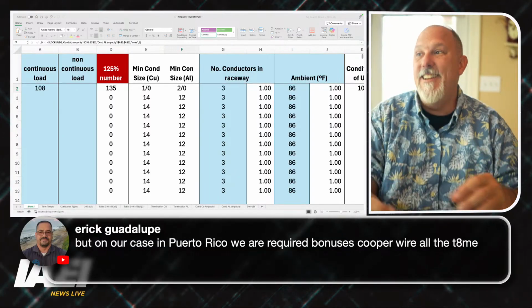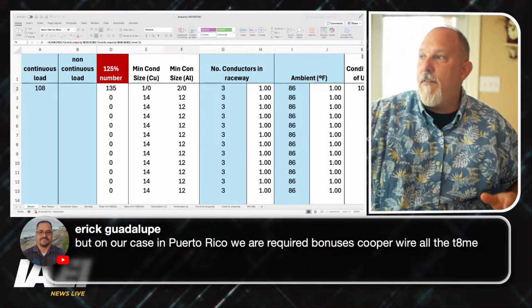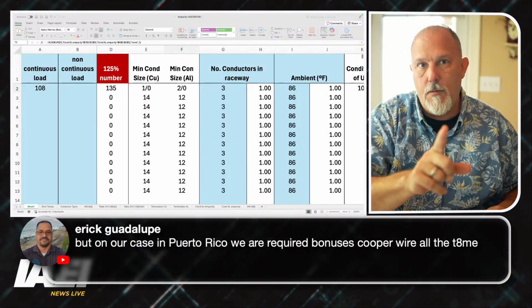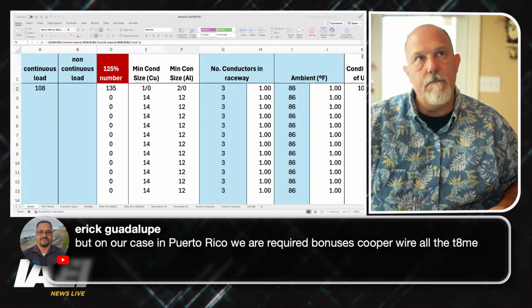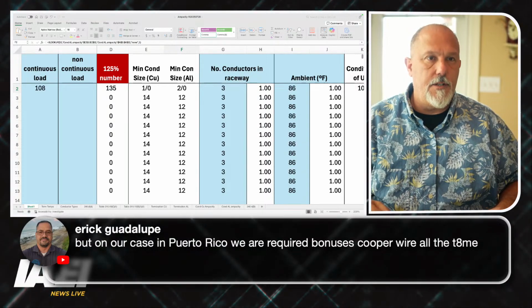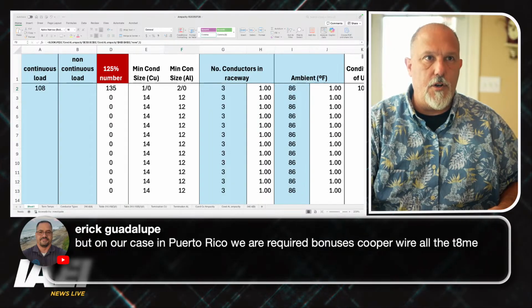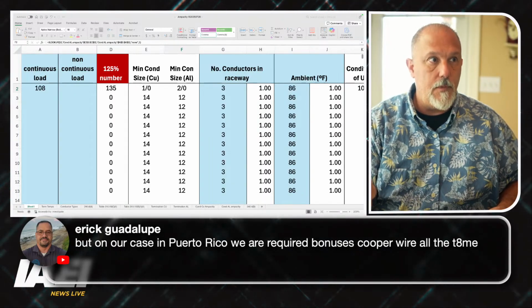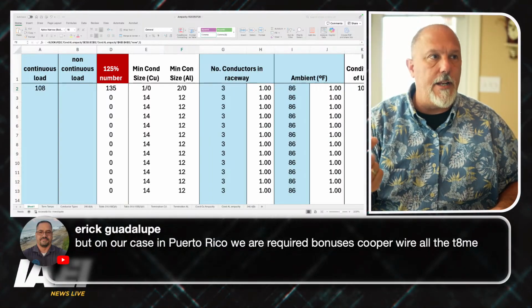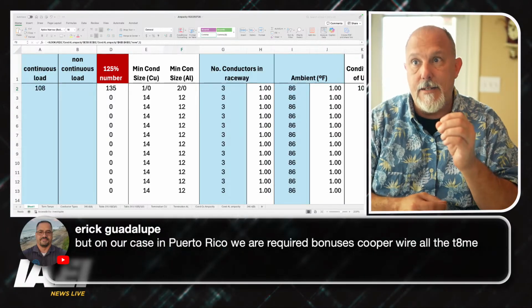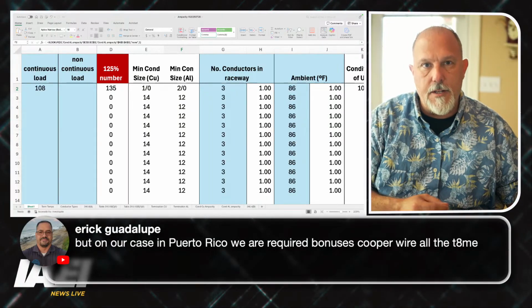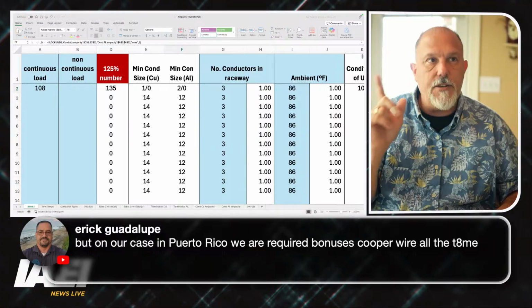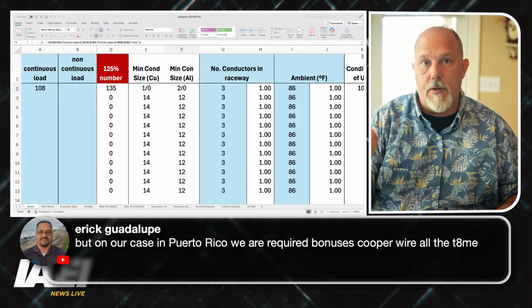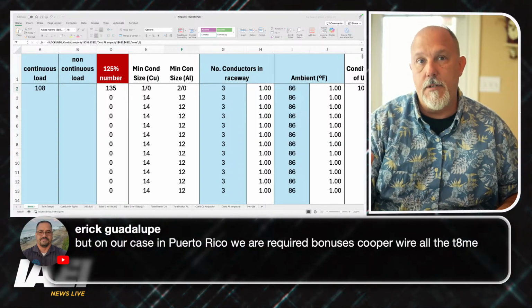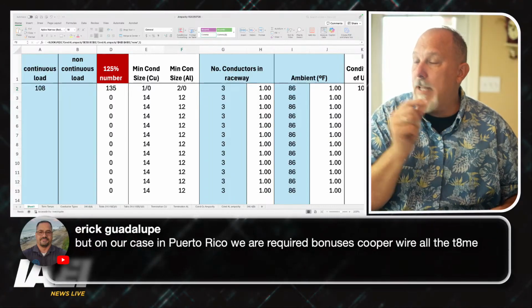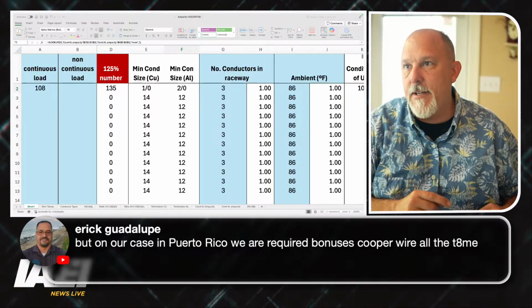So now I need to protect. For 135 amps, based upon, is it 240, I think, or no, is it 215? In Article 210, for overcurrent protection, 210.20 is going to tell you that your branch circuit overcurrent protective device has to be at least 125% times the continuous plus the non-continuous. That's in 210.20(A). In our case, our minimum branch circuit conductor size is 135 amps. It can go larger, but it can't go smaller. But I have that criteria in my spreadsheet a little later.